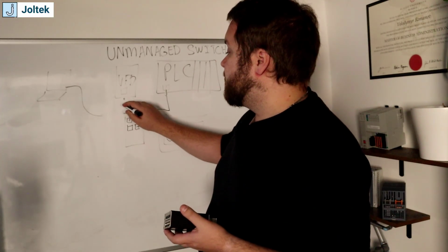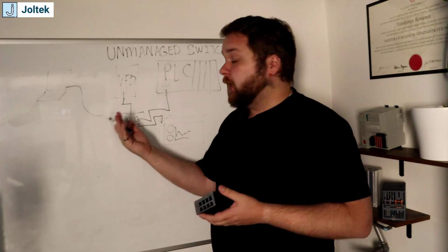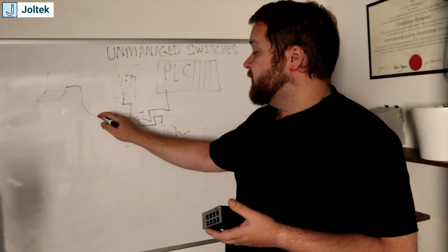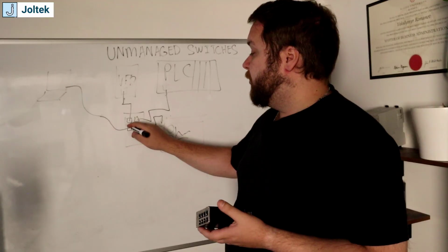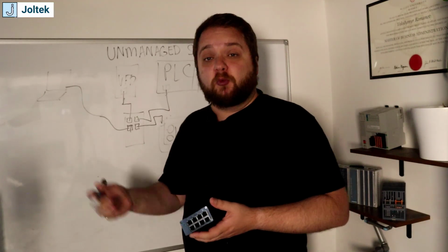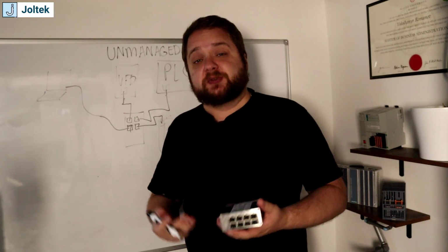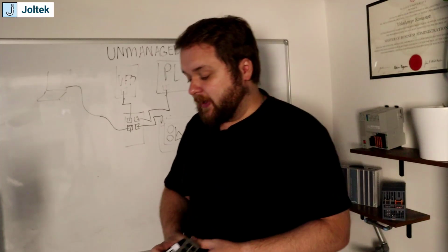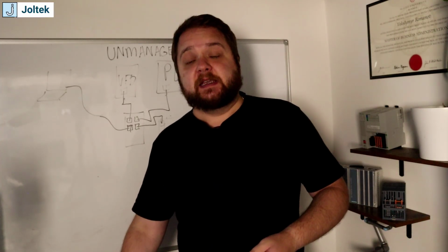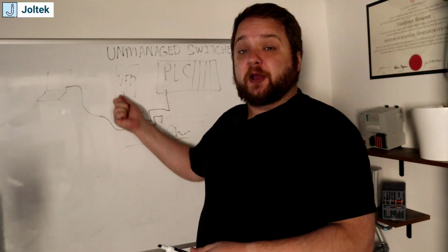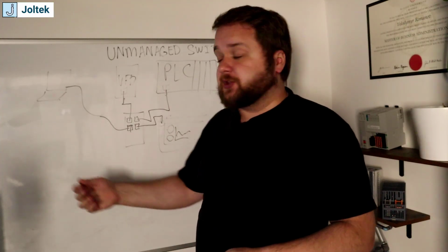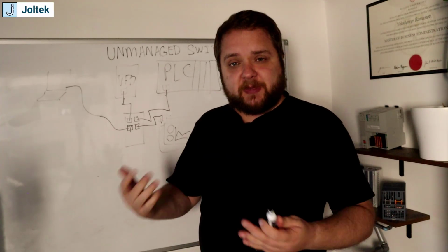And so in this case, I can connect the 3 devices on the same network. I can even plug in my laptop here on the spare port, and I'm able to program while the system is still running, right? So this is one of the advantages of having a switch in your system, is that I don't need to, like I've done before, unplug the VFD to make changes. I don't need to unplug the PLC to make changes.